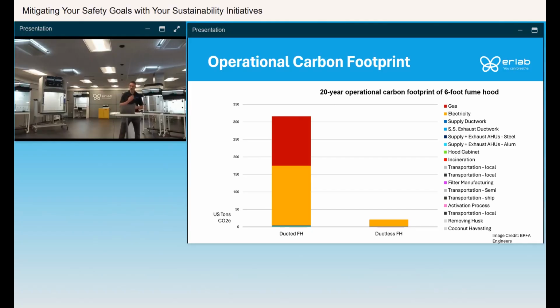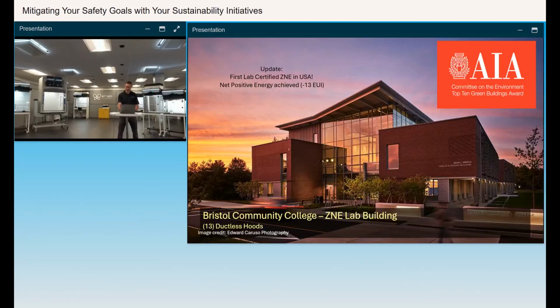Now, if you look at the operational carbon footprint, when you compare over the 20-year lifespan of a ducted fume hood versus a ductless fume hood, you're going to see about a 94% reduction in the overall carbon footprint. And a majority of that has to do with the gas and electricity needed for that makeup air. Because when you're using a ducted fume hood, whatever is being exhausted out that ducted fume hood into the outside world, you're going to need the appropriate makeup air. So in those high-density fume hood labs, that's where you're going to see this significant energy savings.